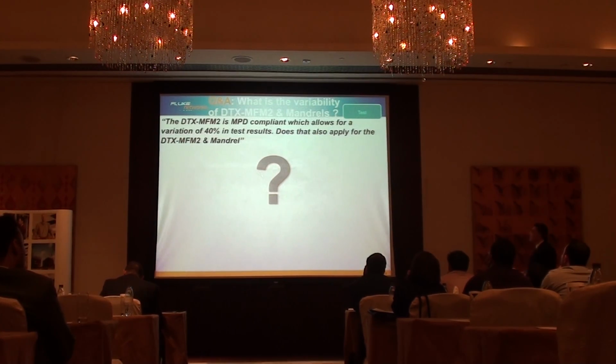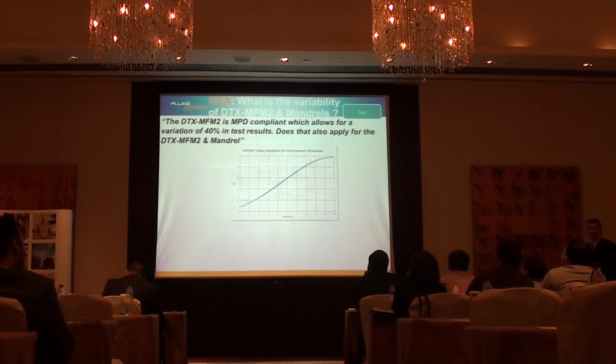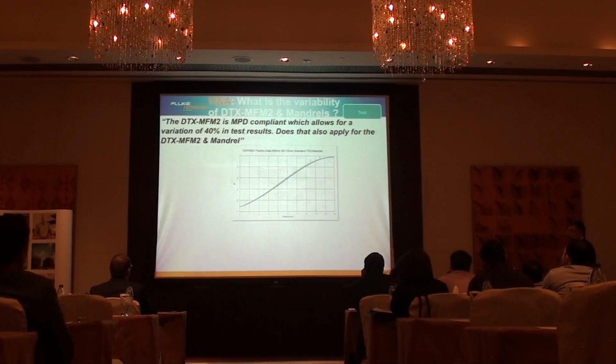MFM2, multi-mode, which a lot of people are using, is it EF compliant or not? The 40% variability that we discussed. Well, I have news for you. Even though it is not EF compliant, Fluke still put it into the encircled flux template and made sure that the combination of the MFM2 and the mandrel will give you what you want. So we fell within that template. Very small variability. It's not encircled flux compliant, it is within the same template.